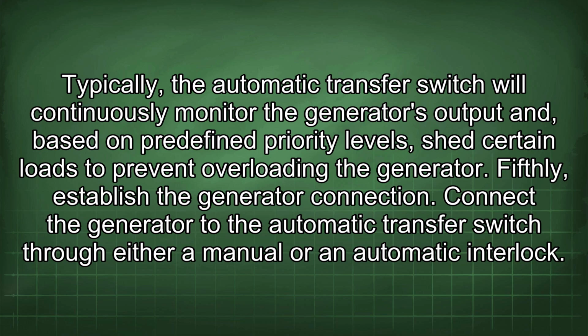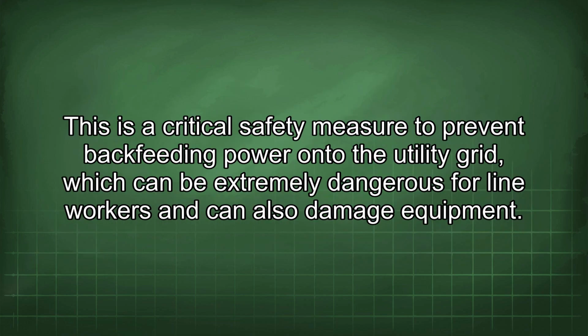Fifthly, establish the generator connection. Connect the generator to the automatic transfer switch through either a manual or an automatic interlock. This is a critical safety measure to prevent backfeeding power onto the utility grid, which can be extremely dangerous for line workers and can also damage equipment.